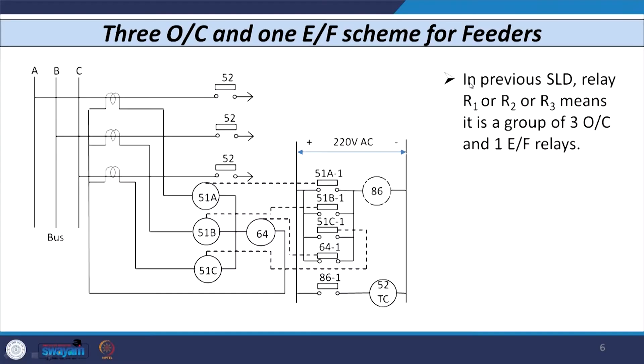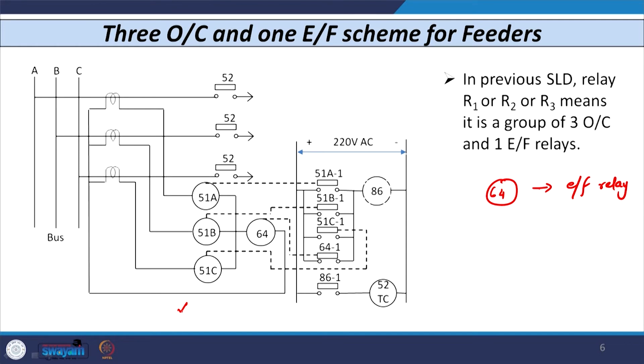Three phase relays are connected in each phase, and in the residual circuit we have one ground relay unit, numbered 64. Number 64 is the designation for the earth fault overcurrent relay. We have a power circuit and we also have a control circuit. The 51A unit has its contact 51A1, the 51B unit has its contact 51B1, and the 51C unit has its contact 51C1.